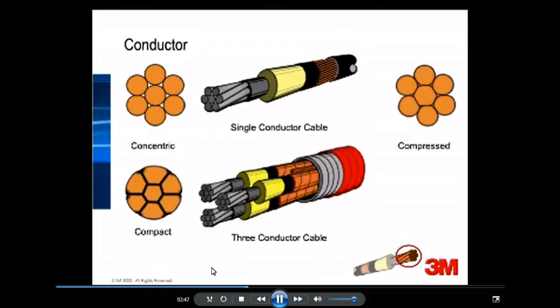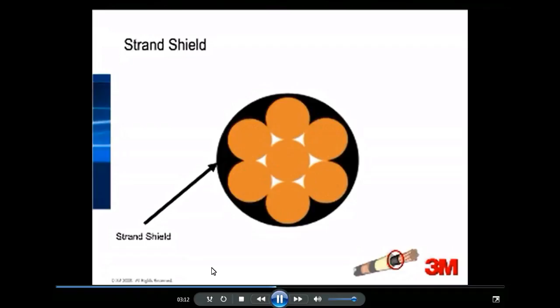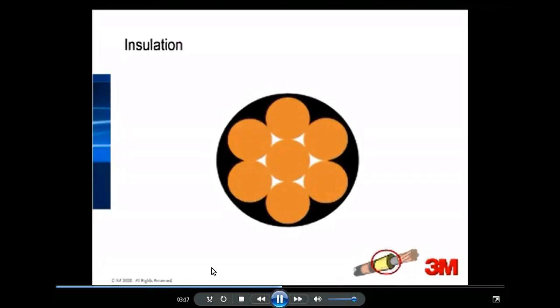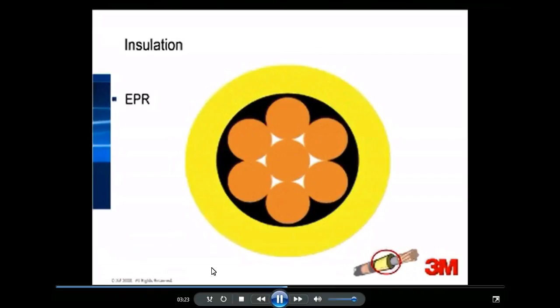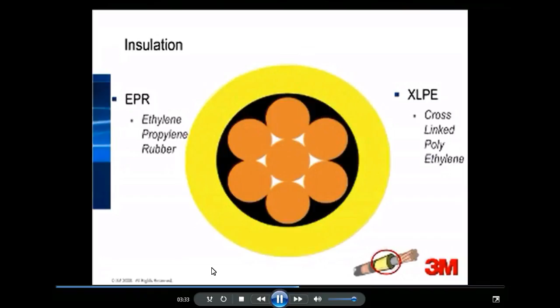The next component is the strand shield layer of the cable. This is a semiconductive layer of the cable. Its function is to shield the cable insulation from any air that may be surrounding the conductor strands. Without this protective semiconductive layer, the air will ionize, resulting in partial discharges. This can deteriorate the cable insulation to the point of failure of that cable. The purpose of the insulation layer is to contain the voltage of the cable. This layer can be made of materials such as EPR, or ethylene propylene rubber, or XLPE, or cross-linked polyethylene. Insulation has a standard operating temperature rating, as well as an emergency operating temperature rating.